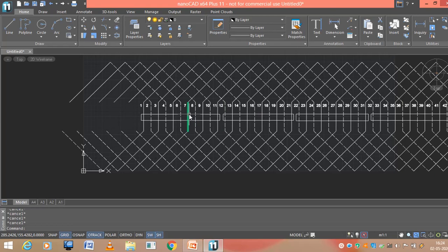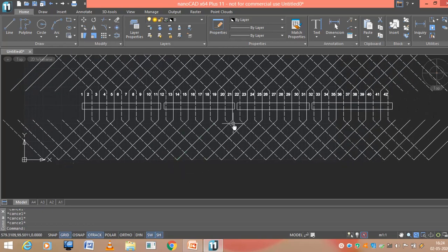See, if you take here also 11, here also 11, then it will become 22. Then you take here 10 and then 10, it will become 20. It is not balanced, right? So north should be 21, south should be 21, and then north and south together it is also 42. Clear? So this is how you can place the poles if you get a fractional pole pitch.